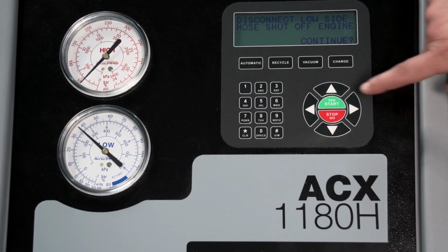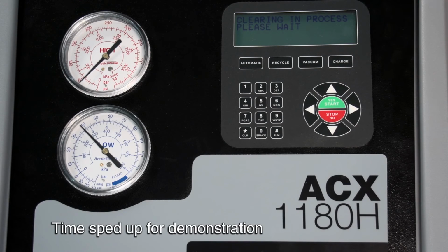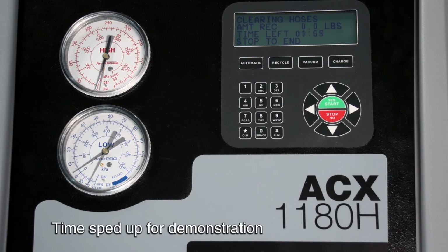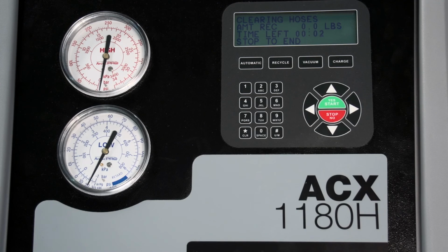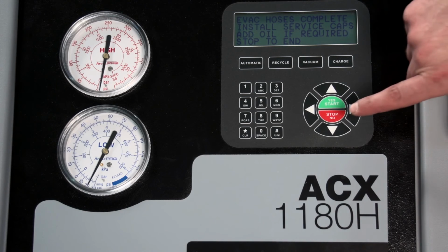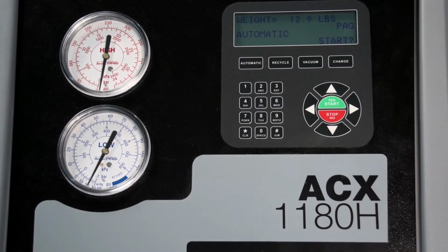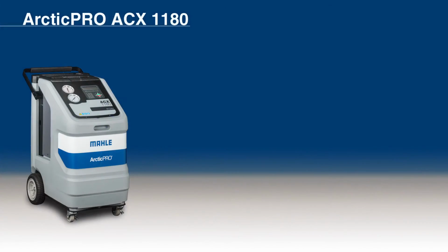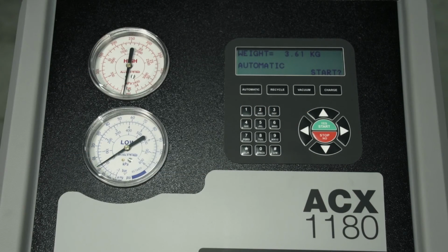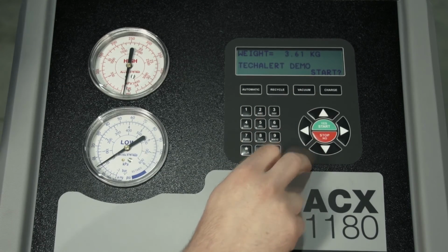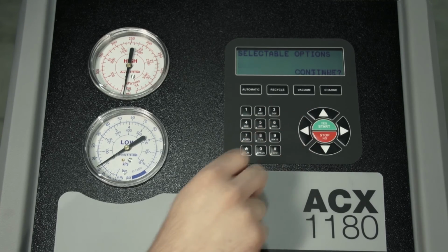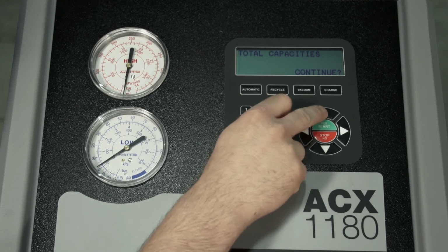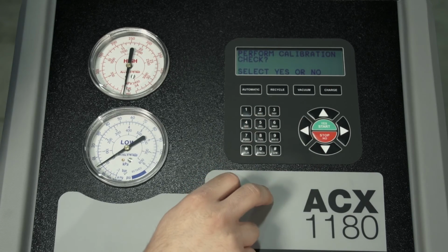Press Start to continue. The machine will go through a final clearing process. Once the evac process is complete, you can replace the service caps and oil if required. Press Stop to return to the main screen. Maintenance. To check the calibration of the machine, press the up or down arrow until the display reads Setup, then press Yes. Use the up or down arrow until the display reads Maintenance Options, and then press Yes.